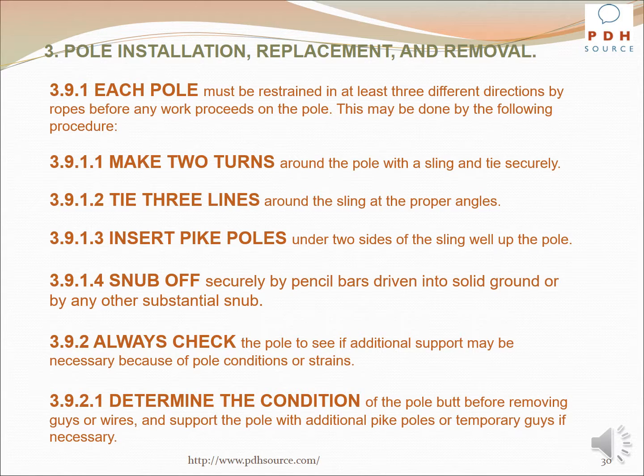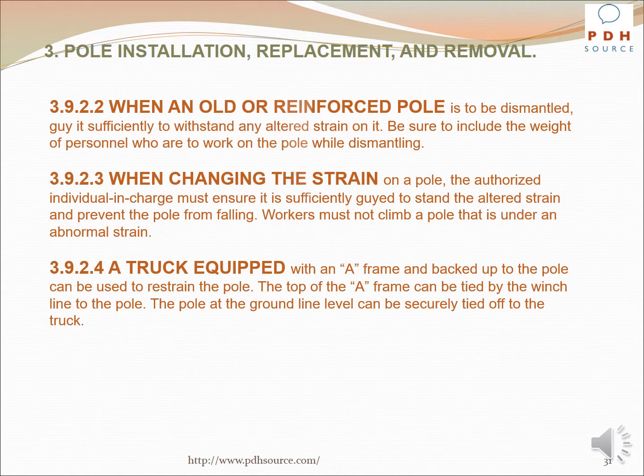Always check the pole to see if additional support may be necessary because of pole conditions or strains. Determine the condition of the pole butt before removing guys or wires, and support the pole with additional pike poles or temporary guys if necessary. When an old or reinforced pole is to be dismantled, guy it sufficiently to withstand any altered strain on it. Be sure to include the weight of personnel who are to work on the pole while dismantling.